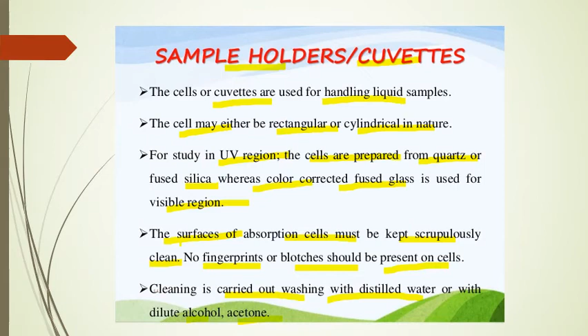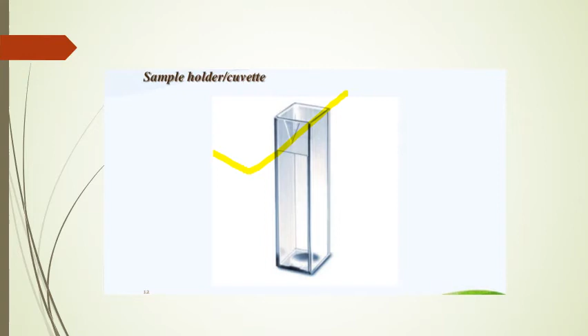spectroscopy. The surfaces of the absorption cells must be kept scrupulously clean. It is very important where we put our sample. No fingerprints or blotches should be present on the cells. So every time we take a sample, we should clean it with the proper solvent so that no fingerprints, scratches, or blotches are on the cells. Cleaning is carried out by washing with distilled water, dilute alcohol, or acetone. So the cleaning of the cuvette and the sample holder is a very important part when we put our sample in the UV visible spectrophotometer. This is the cuvette of the UV visible spectrophotometer, which is made of quartz or fused silica. It should be cleaned with a proper solvent, and only a transparent solution is taken for the analysis.